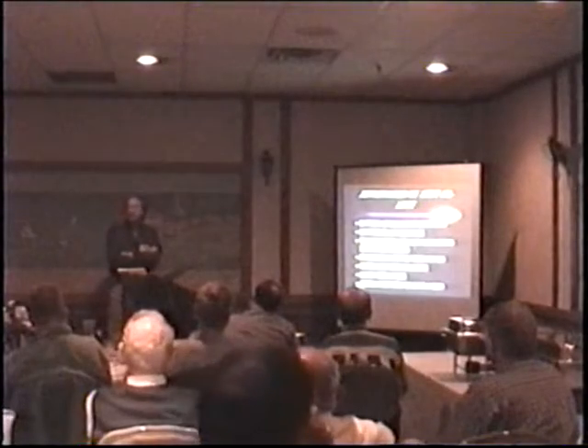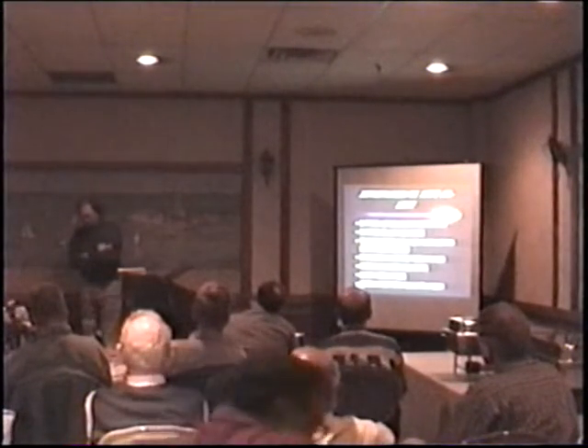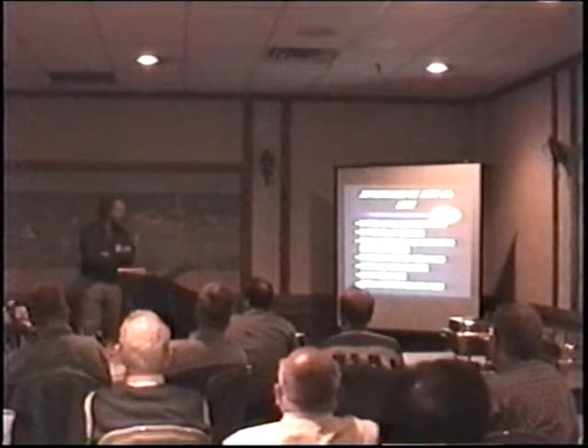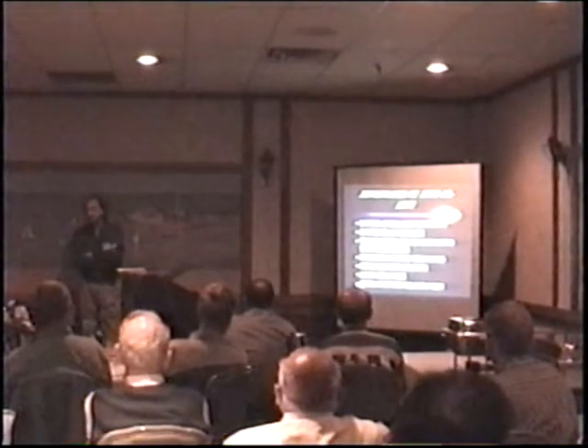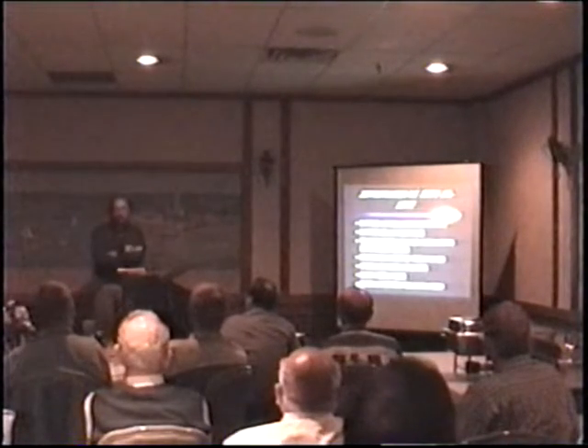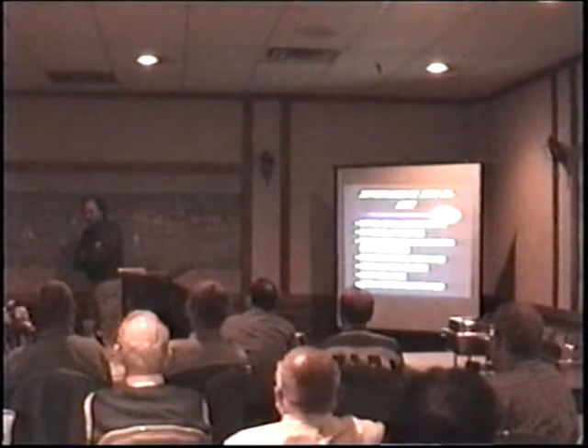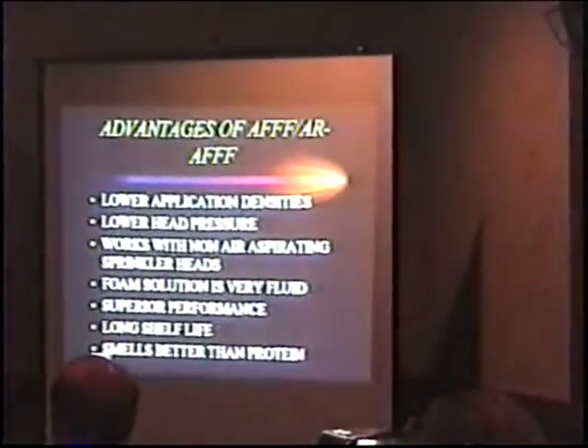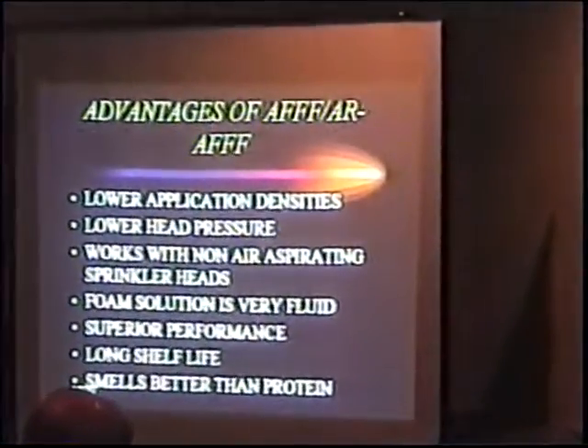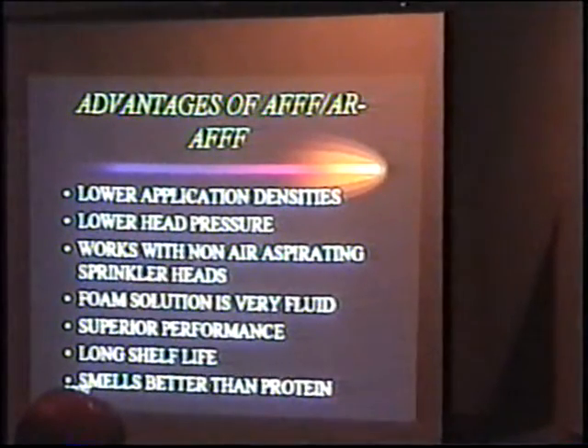Foam solution, once it's on the floor or on the structure, is very fluid. Larger droplets help penetrate the fire plume. Once it's down on the floor, it moves around, gets up on the legs and the beams and other obstacles that may be on the floor. It has superior performance. Tests and actual fire performance have shown that AFFF is probably one of the best out there. It has a very long shelf life. When this stuff first came out, they were scared to say anything beyond 4, 5, 6 years. I think pretty much all the manufacturers out there are saying 20, 25 years and beyond if stored properly. It smells better than protein foam. Anything does. I think anybody would argue that.